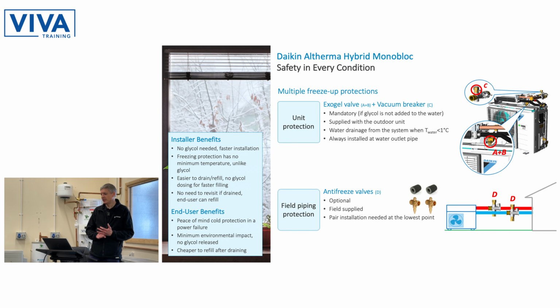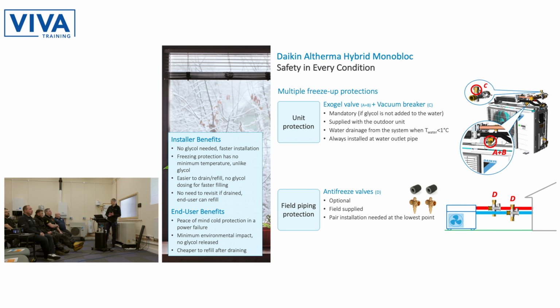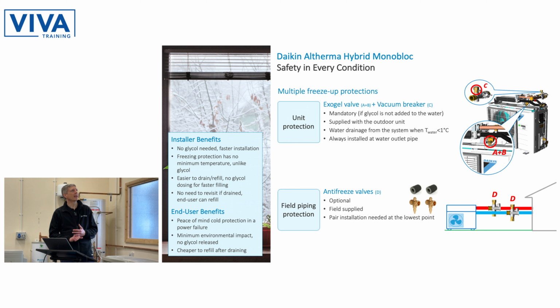So I mentioned safety in the headline. This is particularly the safety of the system, protection against freezing. So we've got a number of levels of freezing protection in this system. I'm not talking about defrost, which is where the air heat exchanger in the heat pump, if that forms ice on it, then that needs to be regularly melted off, and that's our defrost function. So what we're looking at here is the actual freezing protection, the potential for water to freeze in the pipework that's outside the property.